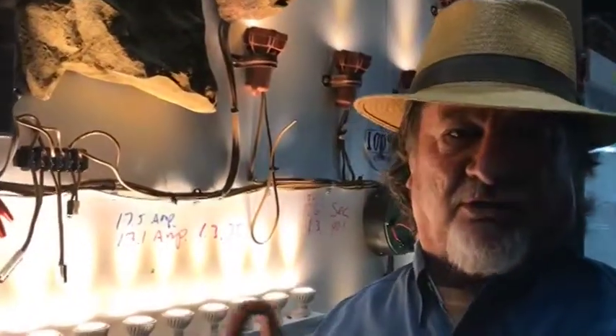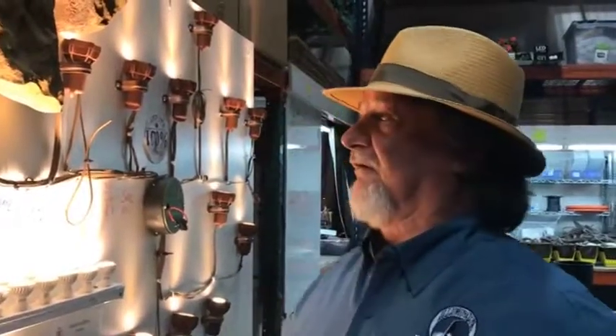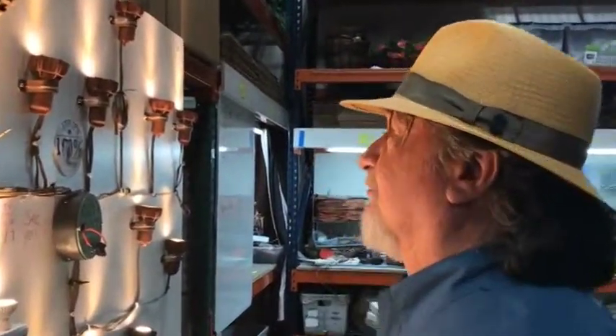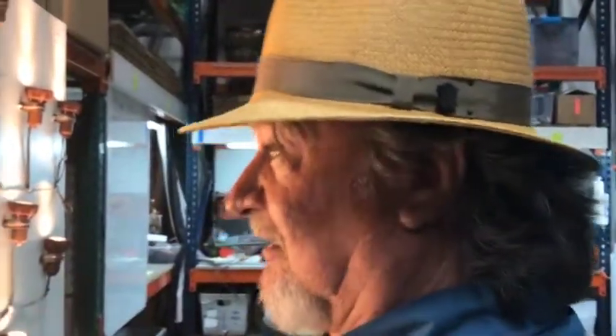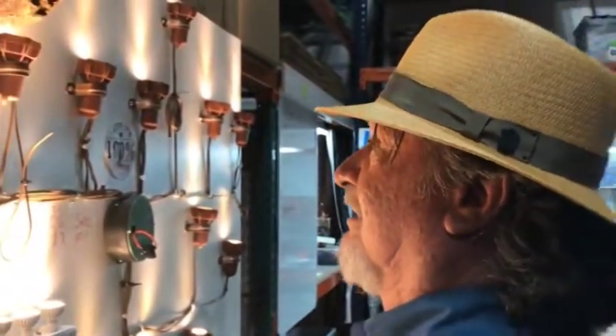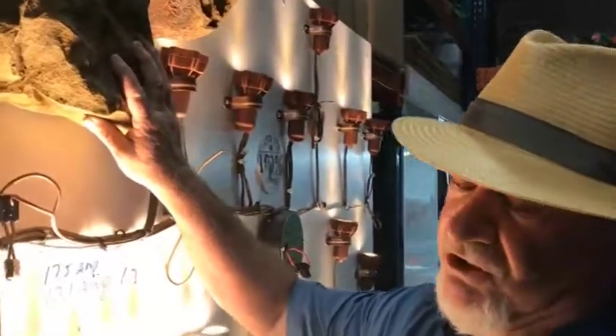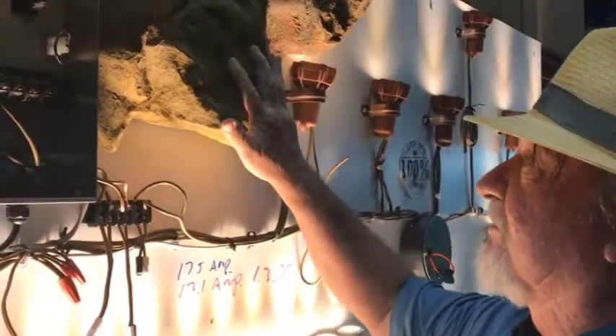Now, all AC magnetic transformers are dumb, all of them. All they do is they have a relative base: 120 in, 12 out; 130 in, 13 out; 110 in, 12 out. That's all they do. They regulate it through this normal set winding pattern. They do nothing else. Where a power supply that's intelligent does a lot of things. So the other thing, which is kind of cool, is it's a different protection.